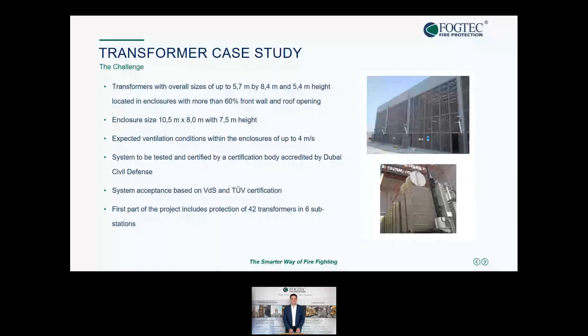In this scenario, we also had to consider certain wind conditions. Looking at the full-scale fire test developed jointly, we built a mock-up again, a one-to-one fire test as is common in water mist technology, where we had to evaluate the performance, following the requirements of NFPA 750 and again the European guideline 14972 standard.